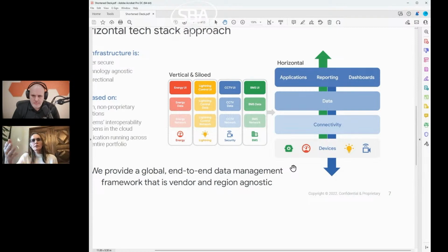And so DBO, digital building ontology, which is now open source, is what we're using to very clearly prescribe how you model a system. How do you define the type of your device? How do you define how it's connected to the other ones? How do you define which data points? How are those data points named? And so the master systems integrator comes in and helps develop this model.